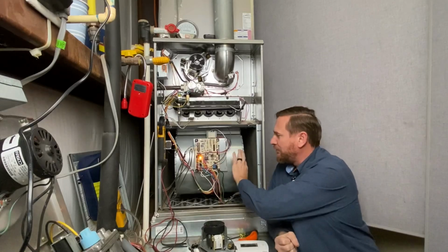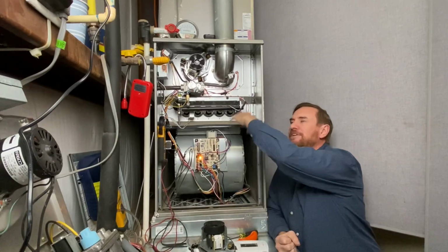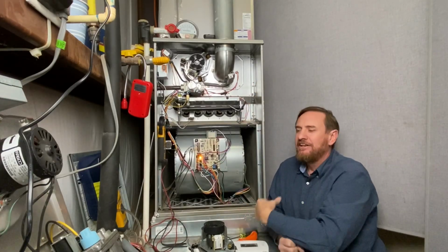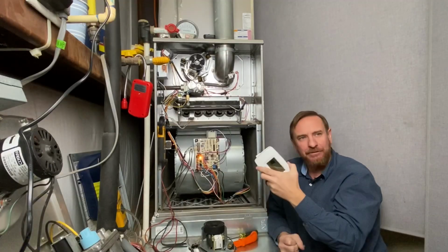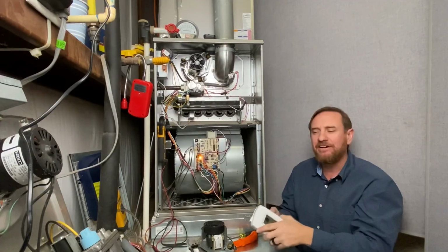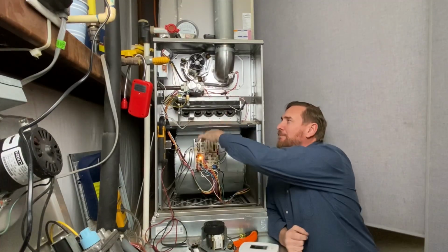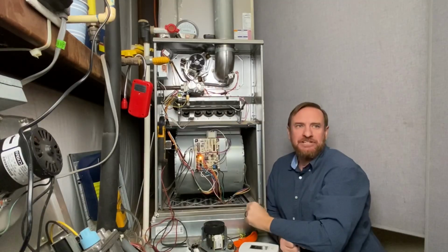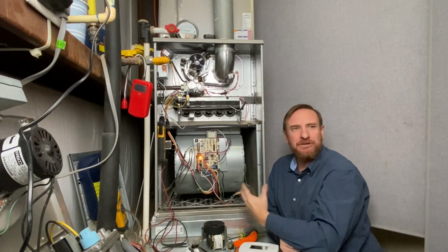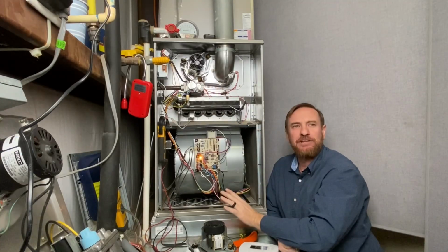We're sending 120 volts to this blower. Now we're moving the air in through the house. So the house heats up. The thermostat's going to want to satisfy, breaking R and W. When it breaks R and W, it immediately shuts off this combination gas valve, immediately killing those flames. We don't need heat. We're going to shut those flames off right away.